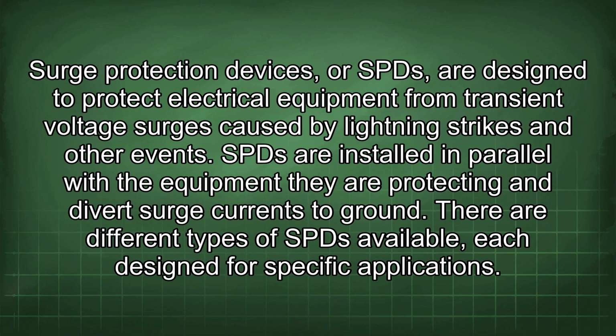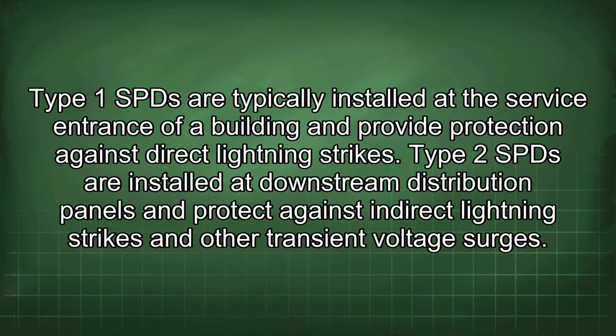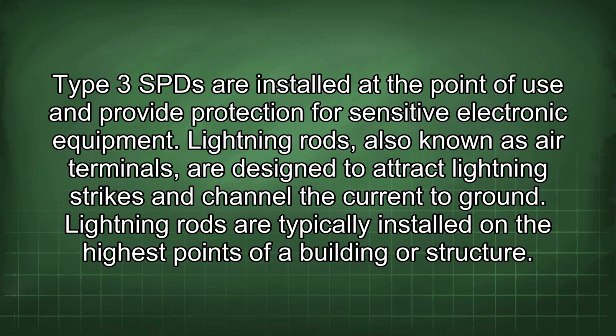Surge protection devices, or SPDs, are designed to protect electrical equipment from transient voltage surges caused by lightning strikes and other events. SPDs are installed in parallel with the equipment they are protecting and divert surge currents to ground. There are different types of SPD available, each designed for specific applications. Type 1 SPDs are typically installed at the service entrance of a building and provide protection against direct lightning strikes. Type 2 SPDs are installed at downstream distribution panels and protect against indirect lightning strikes and other transient voltage surges. Type 3 SPDs are installed at the point of use and provide protection for sensitive electronic equipment.